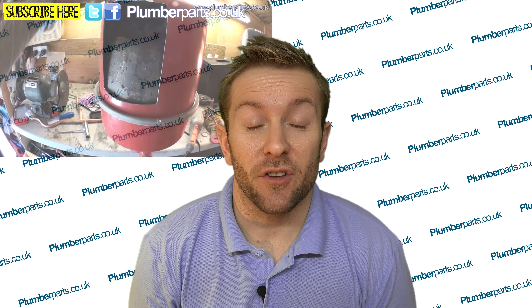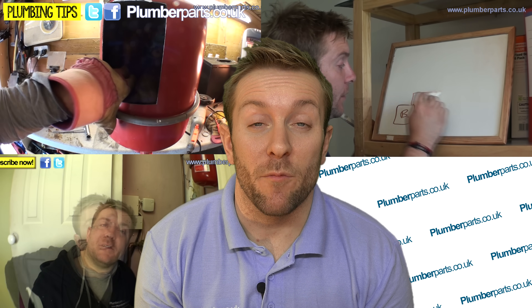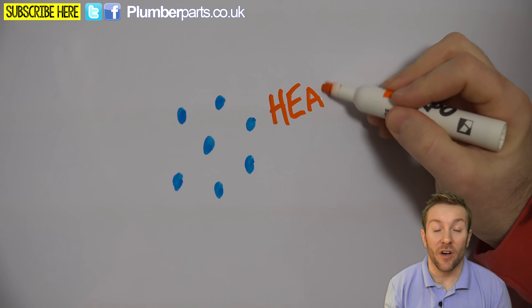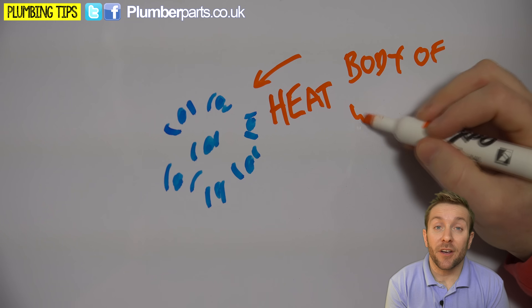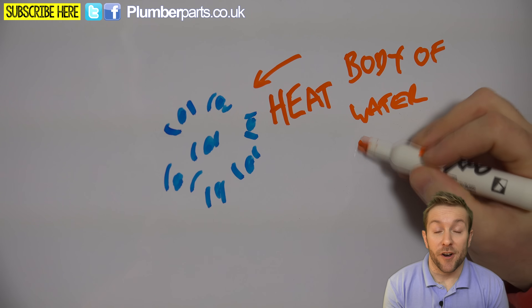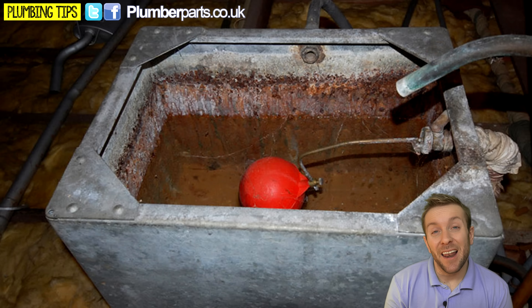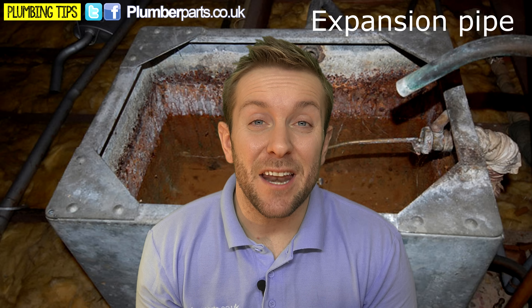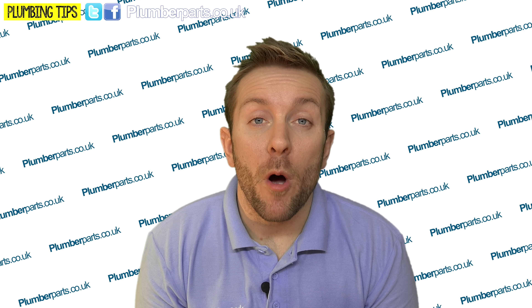You may be aware that we've already done videos on how pressurized heating systems work, and it's quite important to know the basics when it comes to finding out why you've got a problem with pressure drop. When cold water is heated up inside a boiler and inside a heating system, the molecules start to move and get very excited, and because of that, they expand. On an unpressurized system, you have a tank in the loft with an expansion pipe that goes up there, allowing the water to expand up and down without a problem. On a pressurized system, instead of having the expansion pipe, you have what's called an expansion vessel.